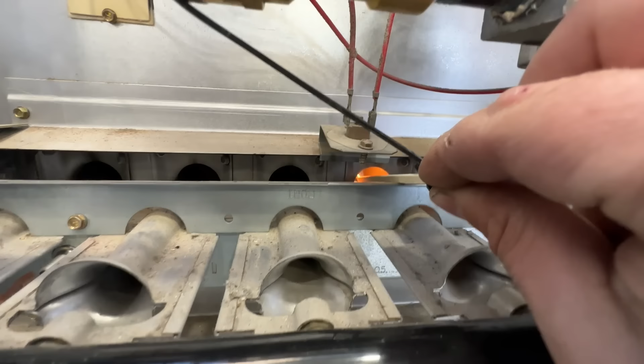Now we're going to do this same test, but with the blower motor on. If there are any holes in the heat exchanger, that air is going to be pushed into the tube and it might actually put out our flame. So if our flame does not dance on any of these with the blower motor on, we've basically just confirmed that we don't have a cracked heat exchanger.